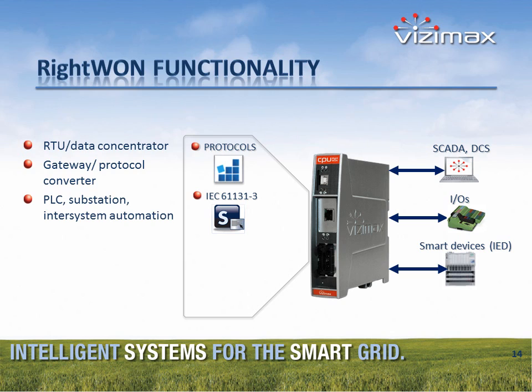The RightWON product also supports an IEC 61131 automation platform. So besides being an RTU, the RightWON product is also a PLC enabling automation of substation or inter-system automation. For example, it can read I/O points from one device, making computation on them and transferring the result back to another device. For example, it can also interlock a circuit breaker based on the position of the switch on both sides of the circuit breaker.